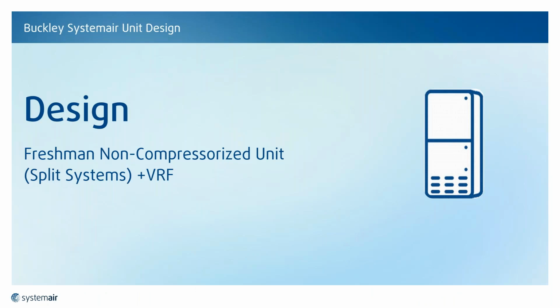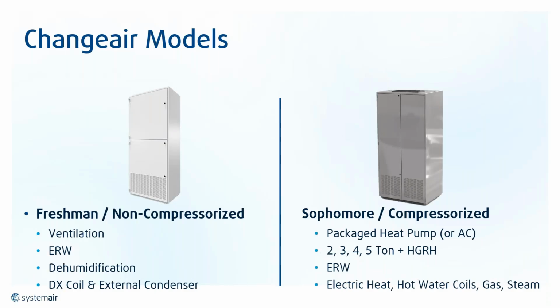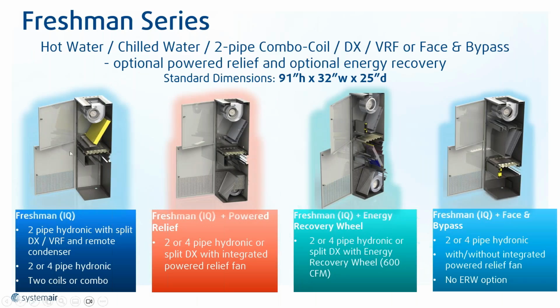Now, if you focus a bit more on the freshman non-compressorized design, the freshman is what we call our more flexible cabinet, just because it was the one that started our Changeair, and then there's been a lot added to it or can be modified to it. So it gives you the option to have straight ventilation mode, energy recovery wheel, you have a dehumidification version, and then you have DX coil with external condenser or VRF. So again, 4 main flavors. You could have face and bypass, with or without the energy recovery wheel, with or without powered relief. You can see the powered relief module at the bottom there. And then you have freshman IQ standard.